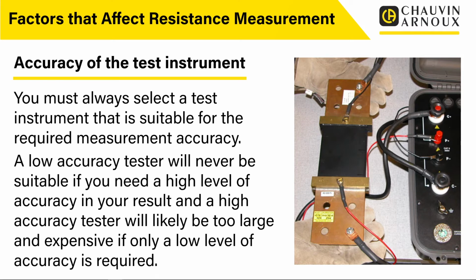But the other way round, if you're trying to look for, say, contact resistance on a contactor, but you're actually using a 2-pole tester that's only accurate to point something of an ohm, you're never going to see anything in the results. The results are just going to be up and down. The accuracy of it is not there enough for you to see what you're doing, and you just end up chasing your tail.